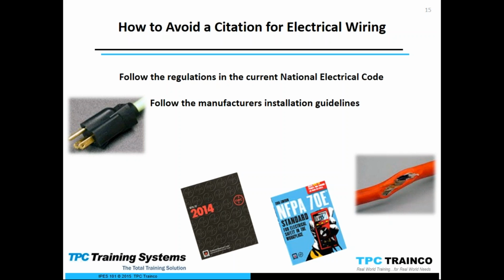Follow the manufacturer's installation guidelines. This is extremely important. In section 110.3(b) of the National Electrical Code, it says you have to install equipment in accordance with the manufacturer's instructions, and you also have to use that equipment in accordance with those instructions. It's very important that we don't just throw away all this information the manufacturer gave us.